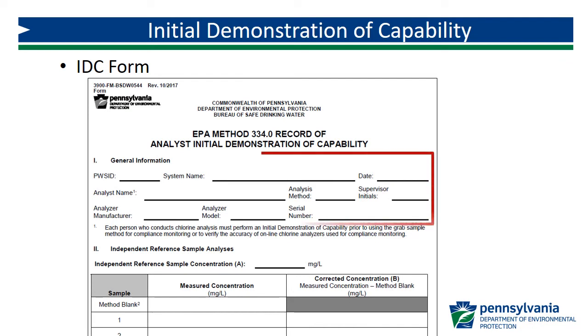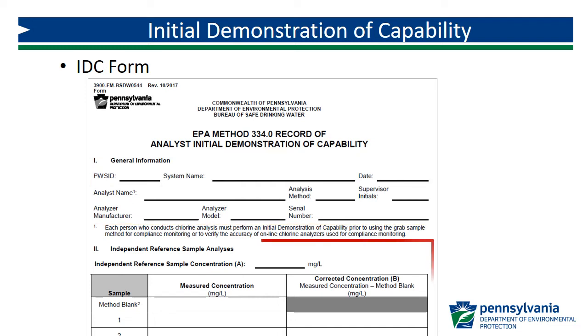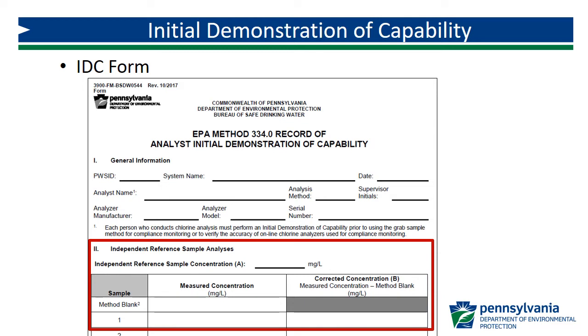Here is what the IDC record-keeping form looks like. You should begin by completing Part 1, General Information, at the top. Record your PWS ID, system name, the date, the analyst name, analysis method, and the analyzer manufacturer, model, and serial number. Part 2, Independent Reference Sample Analysis, is where you will record the results of the method blank and your five replicates of primary standard.